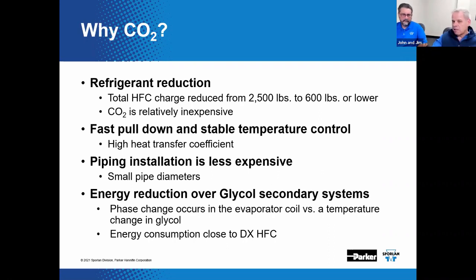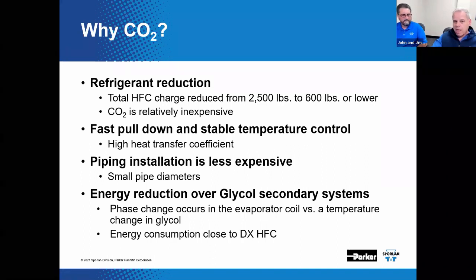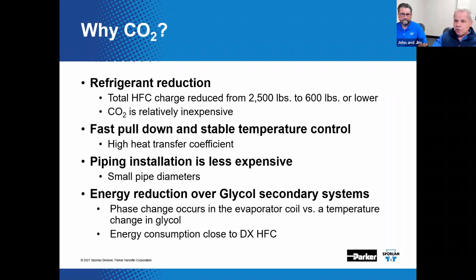as high as 3,000 pounds. Yeah, it would not take a huge supermarket to have a charge of 2,500 pounds. Yeah. But if you use CO2 to cover some of that ground, you can drastically reduce the HFC charge because it's just going to be confined to that one smaller part of the system. And you could then subsequently have an HFC refrigerant charge of maybe in the range of 600 pounds, 700 pounds. And CO2 is relatively inexpensive, all things considered.